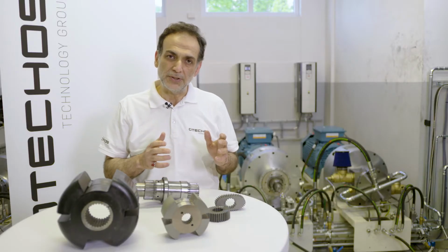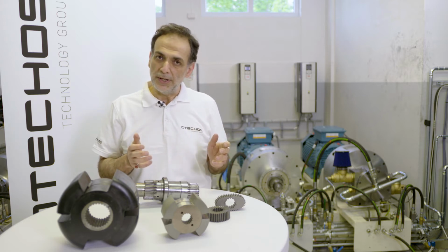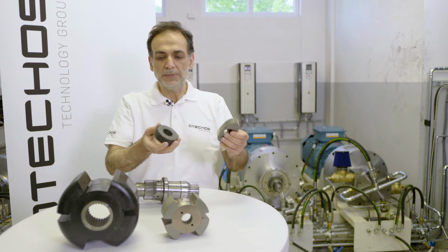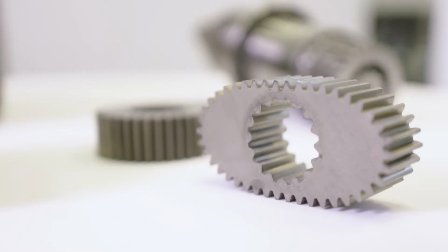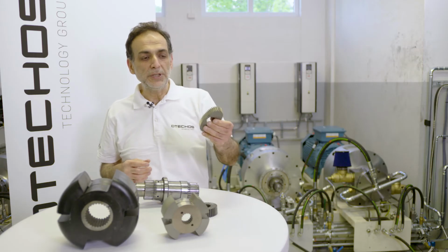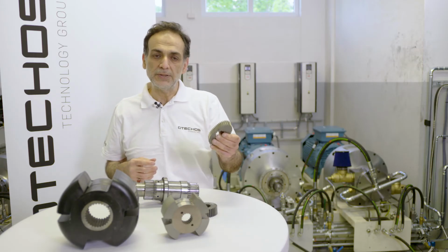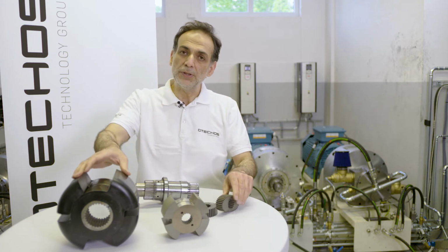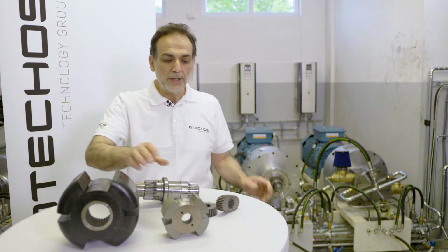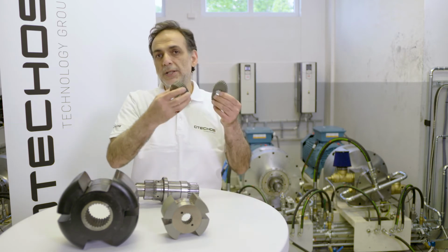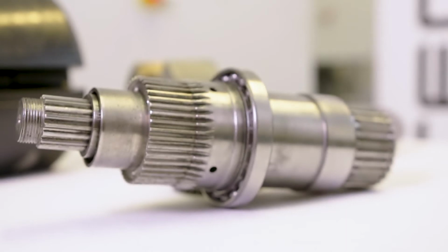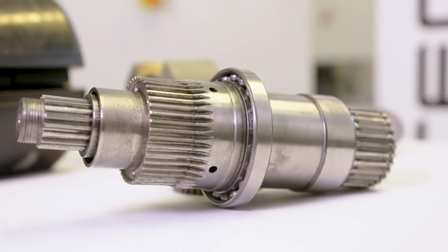The second section of the air end is the control unit, where a number of elliptical and circular gears are at work. The use of elliptical gear gives a unique variable angular velocity to the rotation of the rotors, and that's what's actually causing the compression. The rotation produced by the gears is transferred to the process unit by a pair of coaxial shafts.